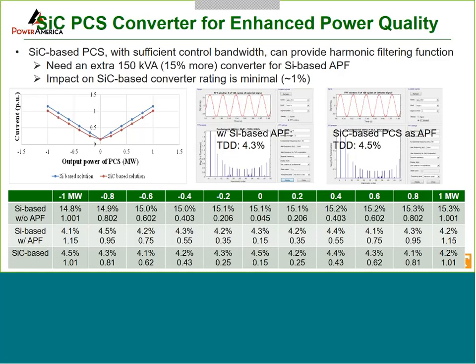With silicon-based approach, because of its limited bandwidth, if you have some harmonic load, you would have to add additional filter, either passive filter or active filter, with a high enough control bandwidth, higher than what medium voltage silicon IGBT can provide. So the difference because of that is about 15% more converter rating you would have to have if you use a silicon-based approach. With silicon carbide, that can be inherently provided with very little impact on the rating, right? It's about just 1%. And in both cases, we can achieve similar THD or TDD.